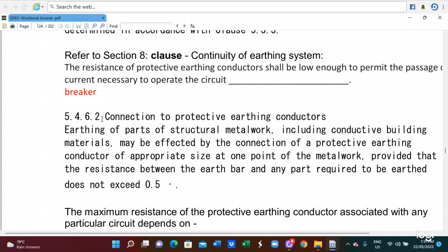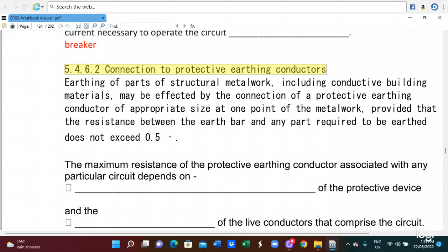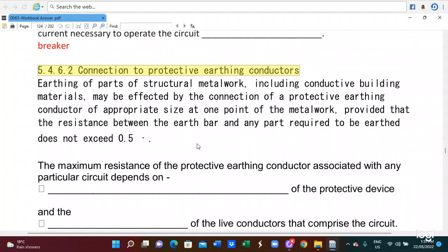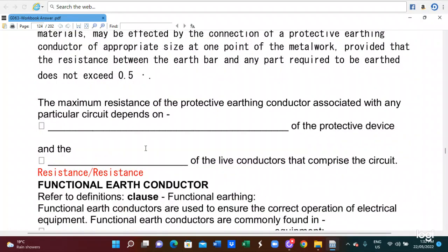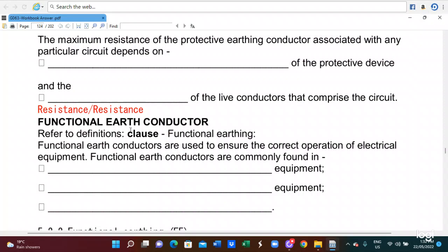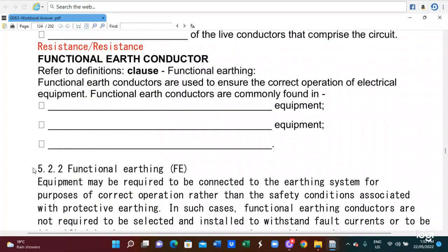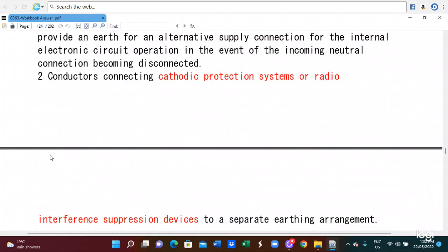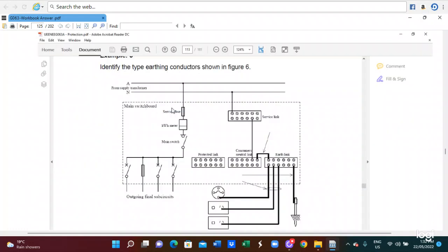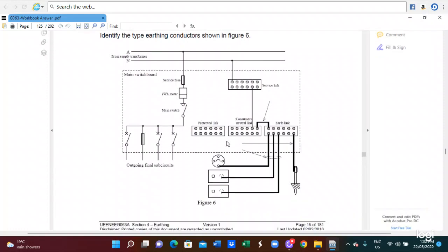And connection to the protective earthing conductor, you have to refer to clause 5.4.6.2. So this is a connection to the protective earthing conductor. All the structural metal work, including conductive building material, may be affected by the connection of the protective earthing conductor on the appropriate size, at one point of the metal work, provided that the resistance between the earth bar and any part required to be earthed does not exceed 0.5. And resistance or the functional earth conductor, you can read in 5.2.2. And also you can read all the RCD connection, cathodic protection. So those are appropriate connection diagrams for the earthing equipment.